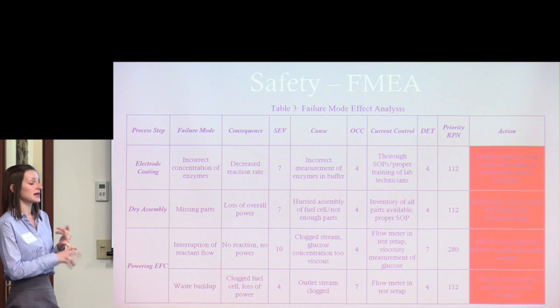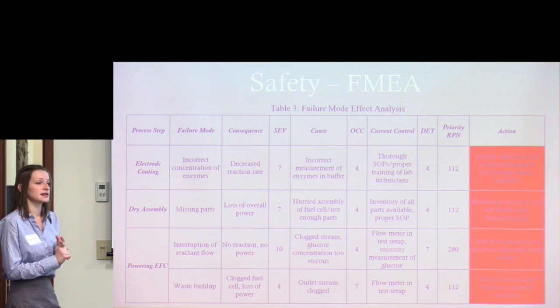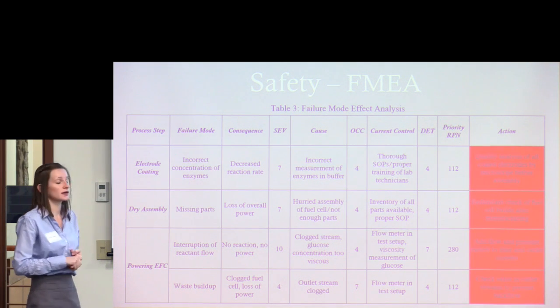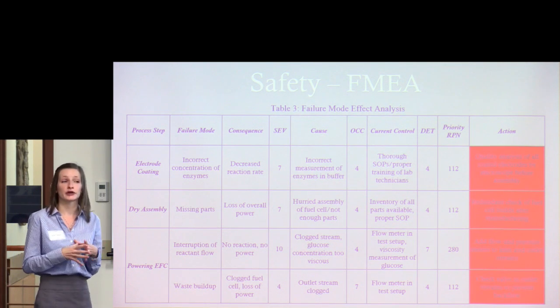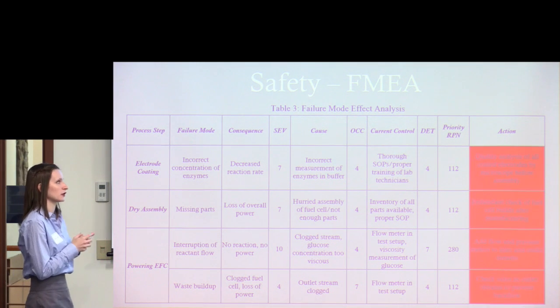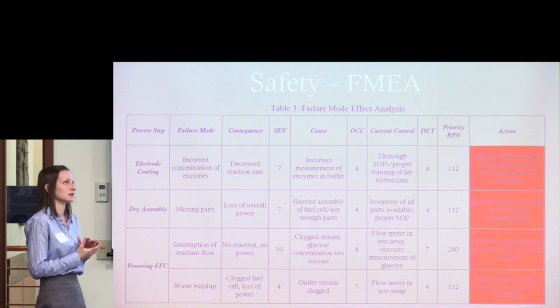So we're going to test the surface area with the BELSORP Max, test the thickness with a micrometer, and also look with the laser scanning microscope to see if there are any impurities on the electrodes. We're hoping this failure rate will be low because of training and thorough SOPs.